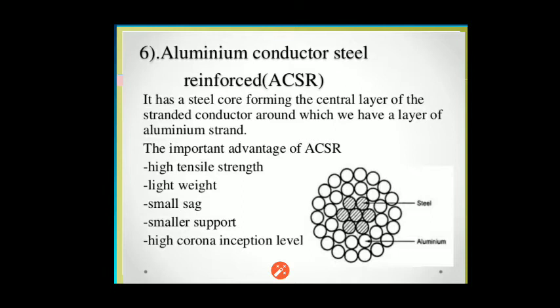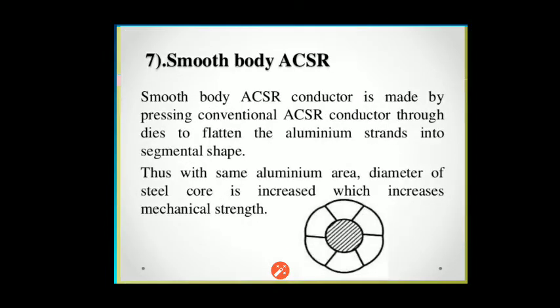Sixth, the ACSR conductor — aluminium conductor steel reinforced — is one of the most important types. It has a steel core forming the central layers, around which there are layers of aluminium strands, as shown in the diagram. Its advantages include high mechanical strength, light weight, small sag, requirement of smaller line supports, and high corona inception levels.